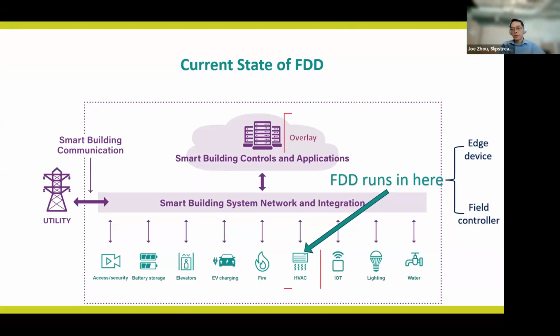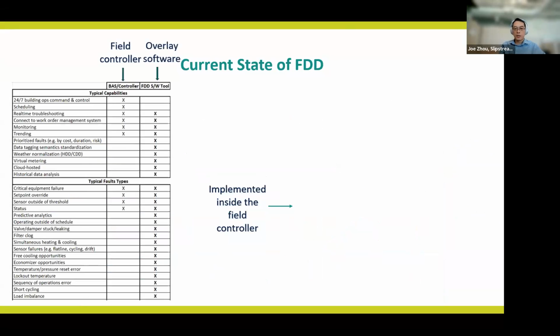So what's the difference between the different ways of running AFDD? This table, embedded in the ASHRAE handbook, shows there's much more limitation in what you can do at the controller level, because there's limited storage and limited calculation blocks you can use when writing custom AFDD or fault detection diagnostic logic.